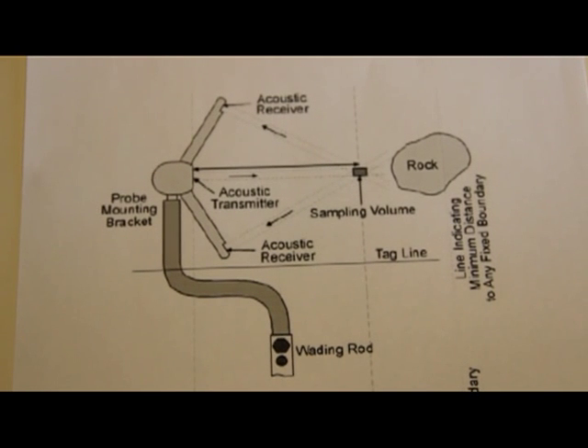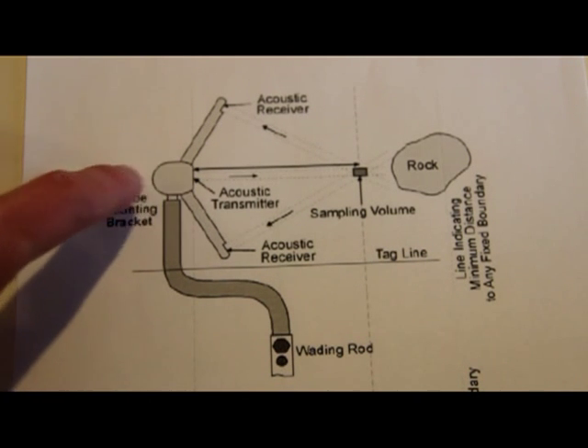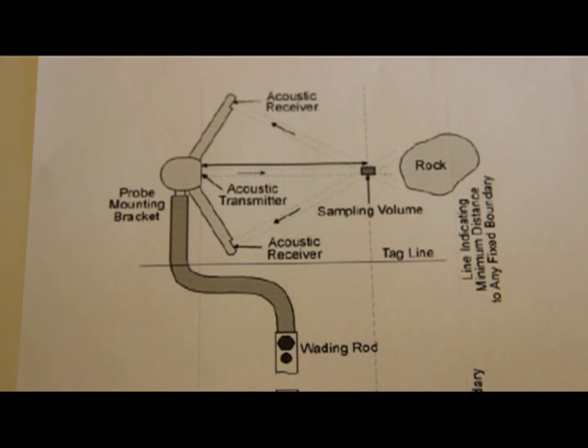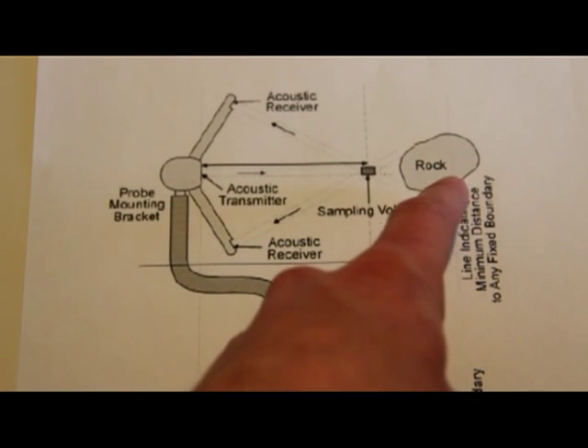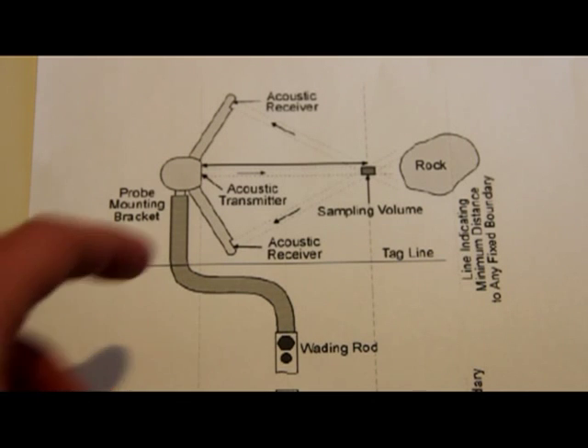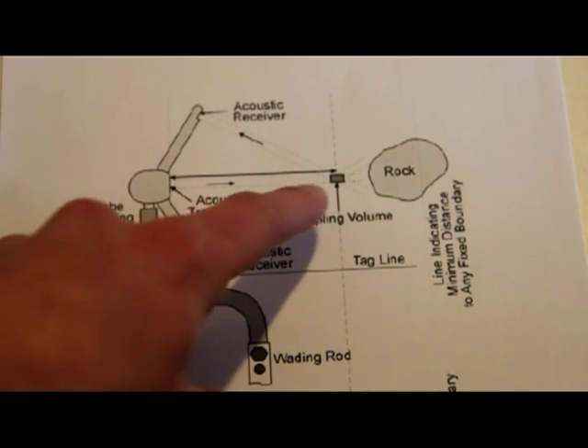The flow tracker uses acoustic doppler to track sediment in the water to calculate the velocity. The flow tracker head has an acoustic transmitter and two acoustic receivers. One thing you have to look out for when making a measurement is boundaries such as rocks — it's good to keep the sample volume at least two inches away from them. The sample volume is located four inches from the acoustic transmitter.